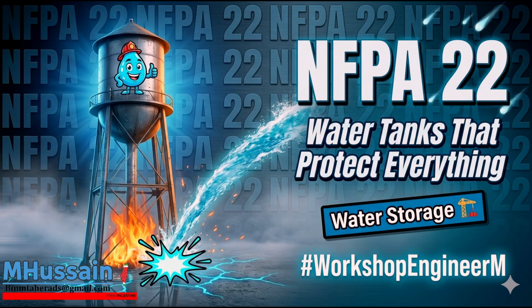Now we have to protect it from the opposite, extreme absolute zero. Section 5 of our outline covers environmental threats, specifically focusing on the battle against freezing, detailed in chapters 15 and 16. A frozen system is a dead system. Period. Whether it's a 2-foot layer of ice on the surface of the tank preventing the float valves from operating, or a single frozen 90-degree elbow in the discharge pipe blocking flow, ice renders the entire fire protection system utterly useless. And the 2023 edition introduced a massive paradigm shift in how engineers must approach frost design.